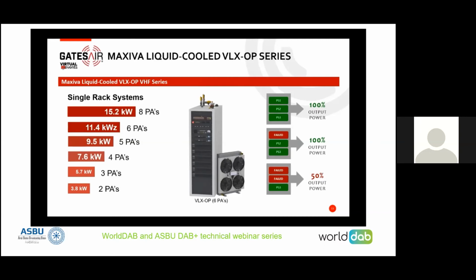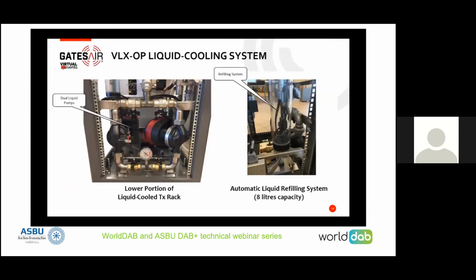It's also important to note, in both the air-cooled and liquid-cooled cases, you see this chart with PS1, PS2, and PS3. In this architecture and in contemporary designs, you'll have multiple power supplies. Somewhat unique to the ones we're showing you, we have N+1 power supply redundancy—so if you lose a supply, you're still at 100%, or if you lose two supplies, you're at 50% power.